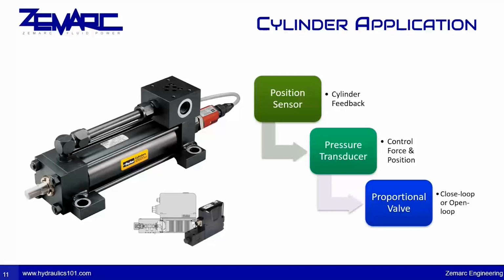Pressure transducer, and this can be used to measure the pressure inside the cylinder, like I stated before, which can actually be used to control the force applied by the cylinder, or just provide feedback on the system's performance. So another thing that's important to touch on real quick is a closed loop system. A closed loop system uses feedback from sensors to control the system's operation, while an open loop system does not use feedback. Closed loop systems can provide more accurate control and monitoring, but they may be more complex and expensive to implement. Therefore, for cylinder applications, you'll need a proportional valve.